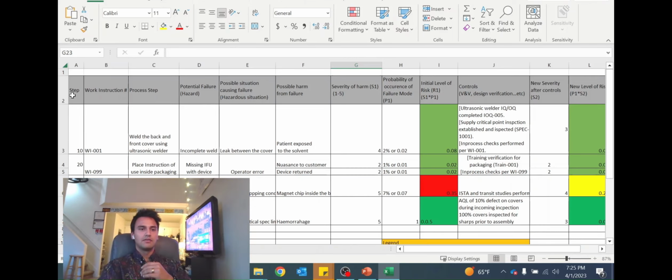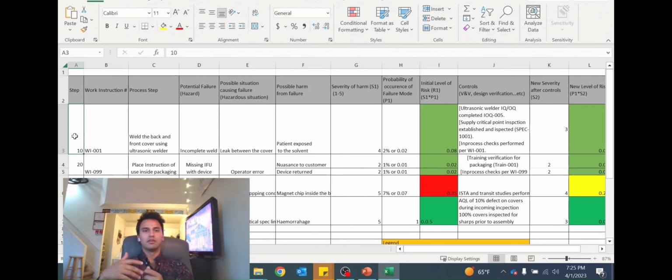So you go ahead, and I made a step first. I guess now you guys can learn how to even make the pFMEA. First you put in steps, and I put 10, 20, 30, 40 instead of 1, 2, 3, 4, because later down the road, from complaint analysis or trending, if we see new harms or a new process addition, then we need to add it to our pFMEA risk management files. So what we can do is insert a line, and now that new line would be 15. I didn't have to do 1.5. And if I need to add anything between 10 and 15, it would be 12, for example. So that's the good thing about doing 10, 20, 30, 40, 50.